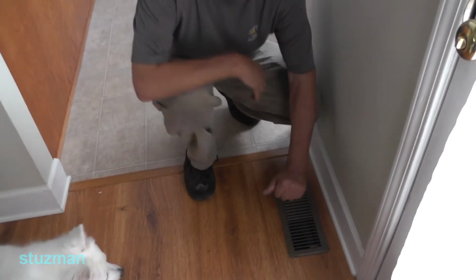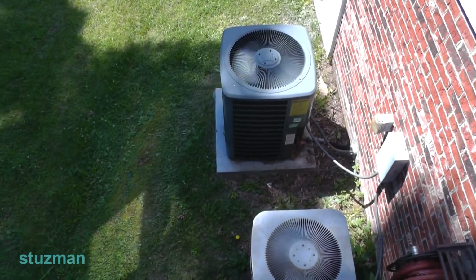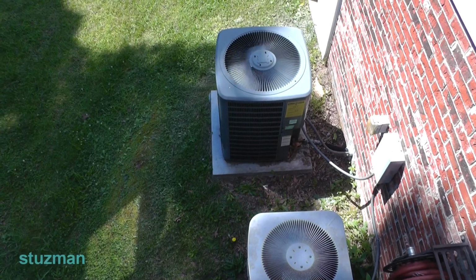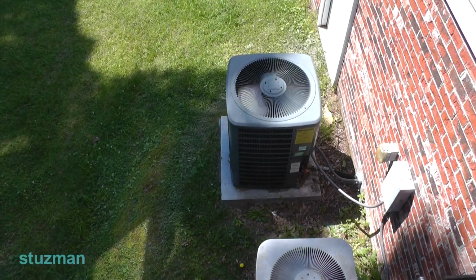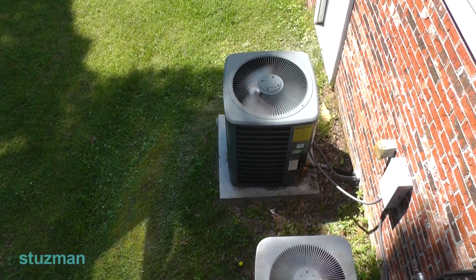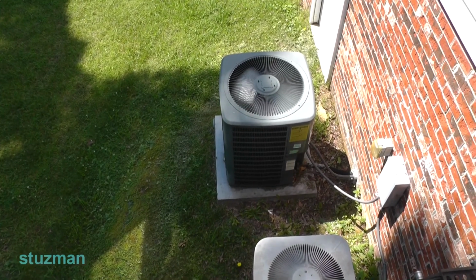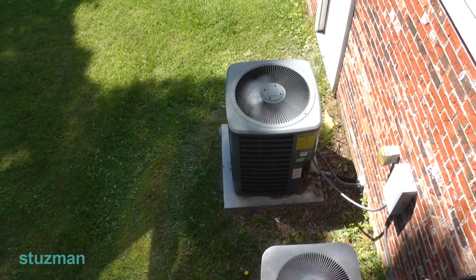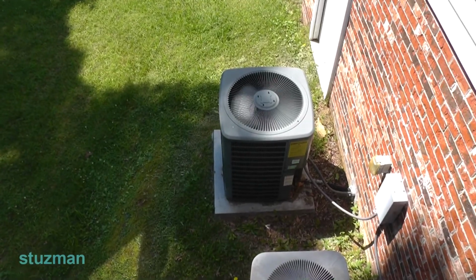That looks good, let's go check the compressor, let's check the condensing fan, let's make sure it's running. Okay, compressor's running, condensing fan is running, and the evap fan is running. So we're gonna give it a little bit and let it run an hour or so. We'll check the temperature, make sure everything still looks fine, and then we'll close this video out after that.